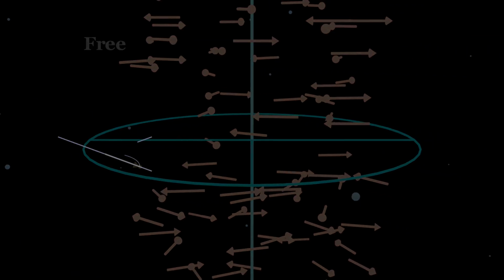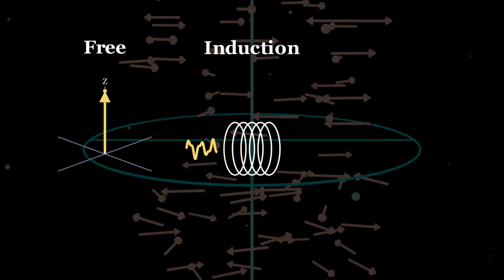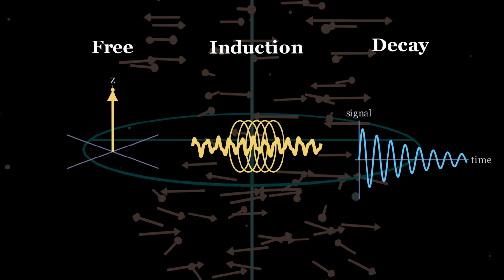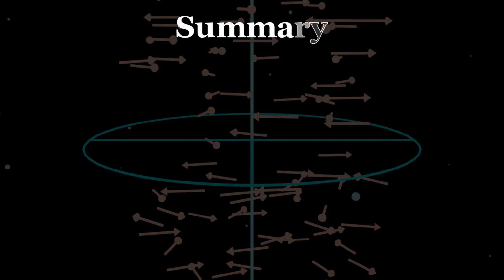The actual signal that we record is called the free induction decay, or for short FID. And it's called free because after the RF pulse ends, the spins evolve freely. Induction comes from the rotating magnetization that induces the current in the coil, and decay because the signal fades as spins lose phase coherence. So in the simplest classical picture, an NMR experiment does three things.